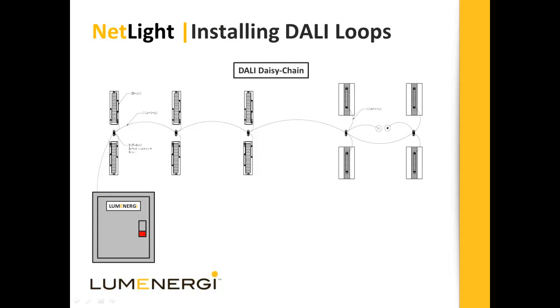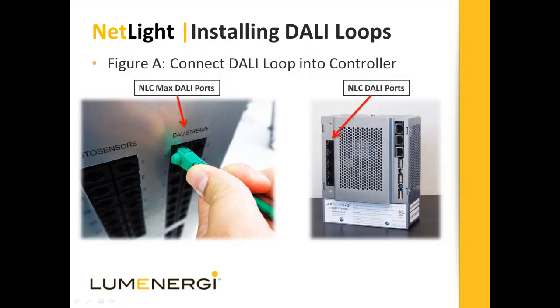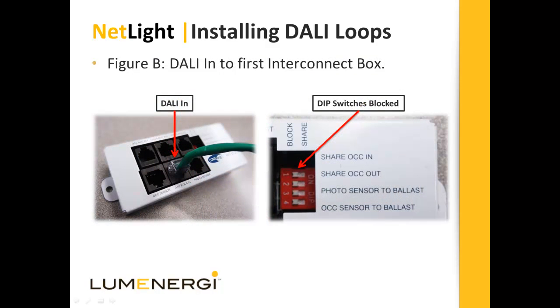To install a DALI loop, the cables should be daisy chained using the interconnect box ports labeled DALI in and out. All ballast and sensors connect to the DALI loop through these interconnect boxes as seen in the example. To install a DALI loop, first connect the DALI cable into the controller's next available DALI port. In this instance, we're starting at the DALI port number 1. The opposite end of the DALI cable should connect into the DALI in port of the first interconnect box. All dip switches should be set to block.